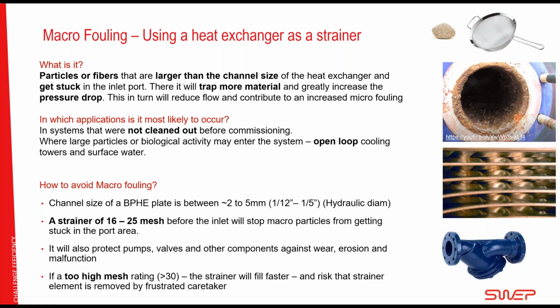If it gets stuck there, that blockage will start to trap more material and greatly increase the pressure drop over the heat exchanger. By doing that, it will also reduce the flow if the pump is the same, right? And that will cause secondary microfouling inside the plate. Where do we see this most often? Well, kind of common is if a system is not cleaned out before commissioning. You will have a lot of scrap inside the closed loop system when you start. That is supposed to be cleaned out during commissioning using filters and strainers and so on. Sometimes yes, sometimes no. So that's a one-off problem, a poorly commissioned system.